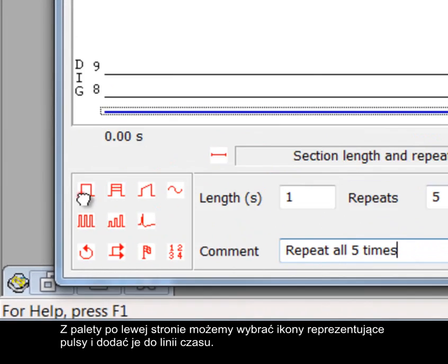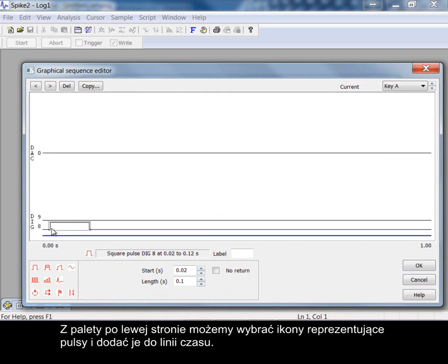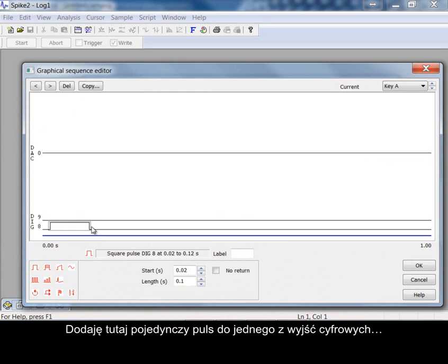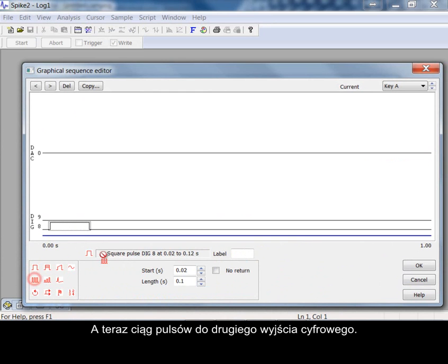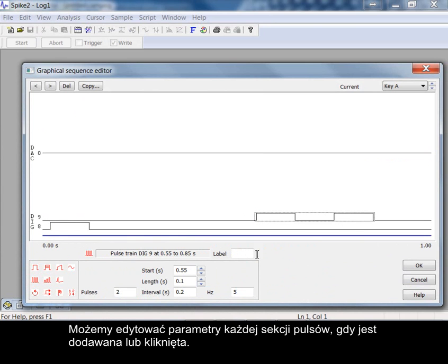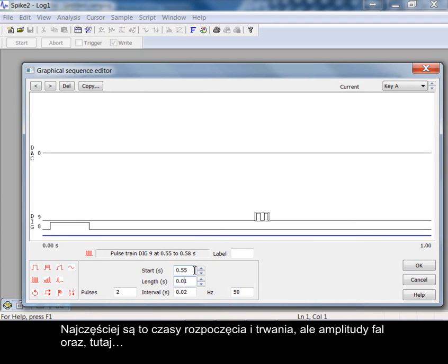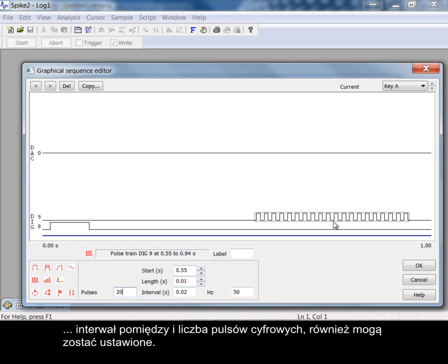From the palette on the left we can select icons representing pulses and add them to the timeline. Adding a single pulse to one digital output here. Now a train of pulses to the other digital output. As each pulse section is added or later clicked on we can edit its parameters. Start times and length are the most usual but amplitude for waveforms and here the interval and the number of digital pulses can also be set.